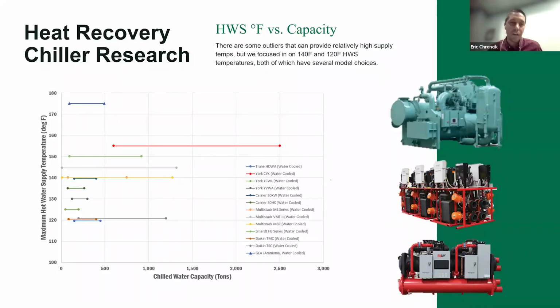While a heat recovery chiller in itself may not have been, because we had a couple installed, it was what manufacturers can meet what hot water supply temperatures, what capacities can you get to, and we developed a graph you see on the left side of the screen here, where we looked at plotting just capacities and temperatures and where things shook out. And for the most part, multiple manufacturers could get to that 130, 140 degree hot water supply temp, although capacity was generally limited. However, that's not the worst thing at the end of the day, because as we're continuing to find out, sometimes multiple compressors give you greater turn down, which at the end of the day, having a unit or multiple machines that can achieve high turn down can really help you when you do have some low load conditions. As Bill was showing on his graph earlier, there were times where the cooling load was almost nothing at all.